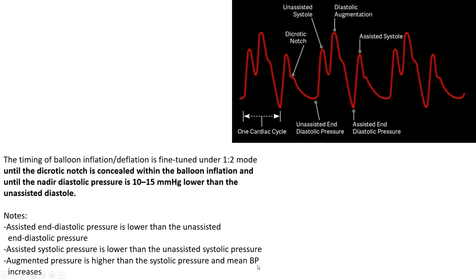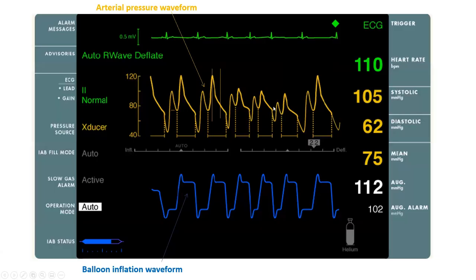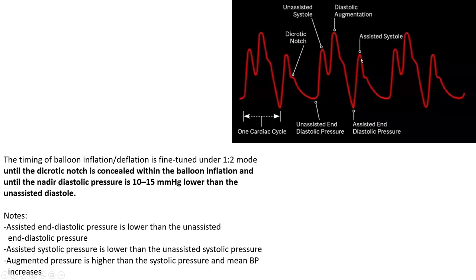Another question that can come up on boards is you may get asked what is called assisted and what is called unassisted systolic and diastolic pressure in 1-2 mode. So when you get balloon augmentation, inflation, keep in mind the pressure that precedes it, that systolic pressure, is not assisted. People may think by reflex, oh, the balloon inflation is coming over that beat, so this should be the assisted systole. No, this is the unassisted systole. The assisted systole is the systolic pressure that will follow augmentation, in the next cardiac cycle. Now, if you're on 1-1 mode, then of course every systolic and diastolic pressure is assisted. But in 1-2 mode, the assisted systolic and diastolic pressures are the ones that follow augmentation. The ones that precede it are unassisted, and you compare those two.